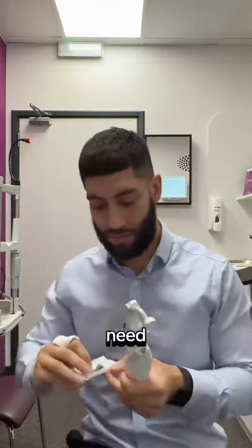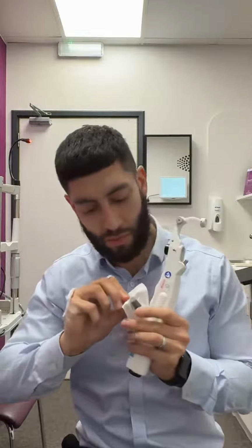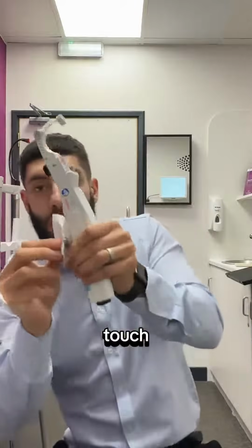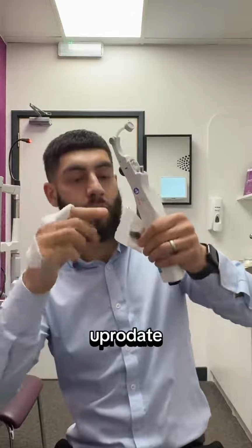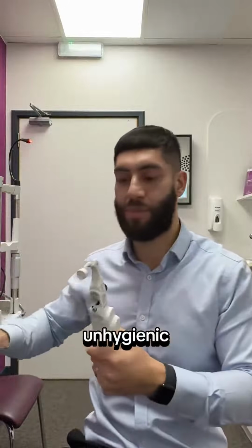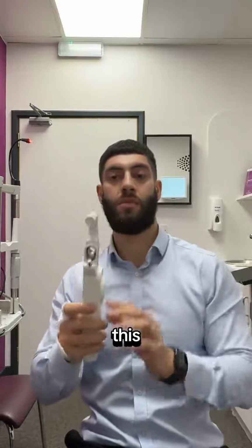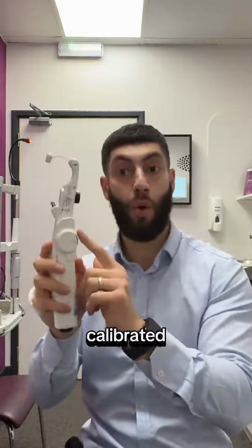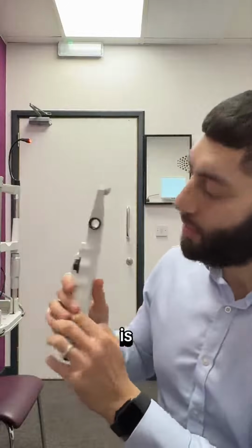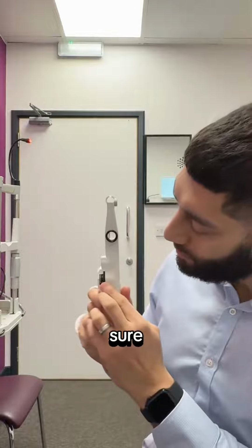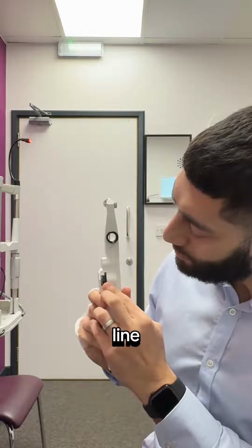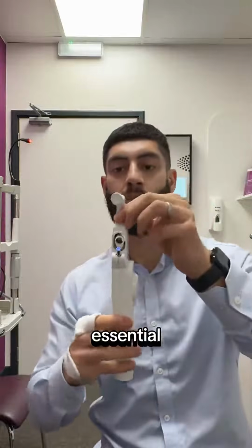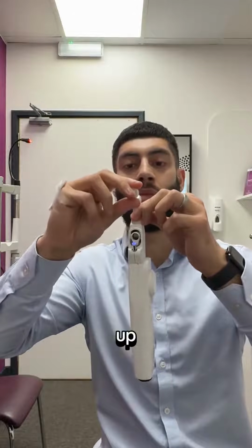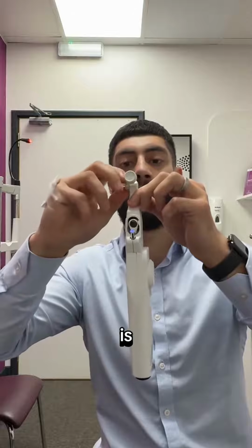So let's get this Perkins tonometer set up. You're going to need to put the probe into the probe slot, but making sure not to touch the area of the probe that will applanate the eye, because that is very unhygienic and not sterile. Now we're assuming that this Perkins tonometer is calibrated correctly. Once the single-use probe is put in, you need to make sure that the line on the probe is horizontal, 180 degrees. This next step is essential. You have to twist the dial to set it up to 10 millimeters of mercury. That is your starting point.